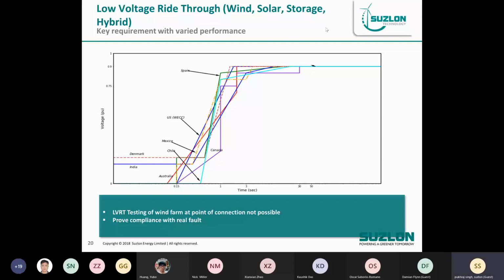In some cases, what you can do is design the turbines or the inverters - we're talking about the park, not individual turbines. But there are no facilities available today to test the whole park. If it's 100 megawatt, 500 megawatt, or even 25 megawatt, we just carry out the measurement at the turbine - at 690 volts or at most 33,000 volts, but not at park level.